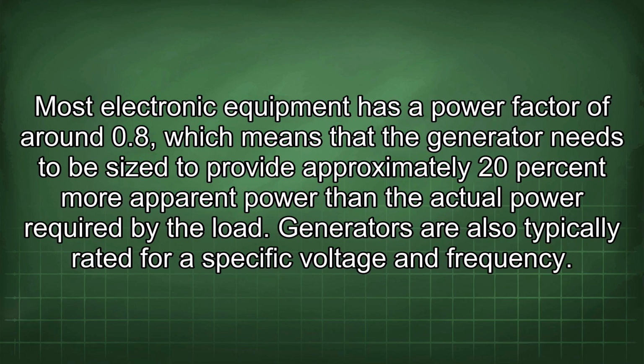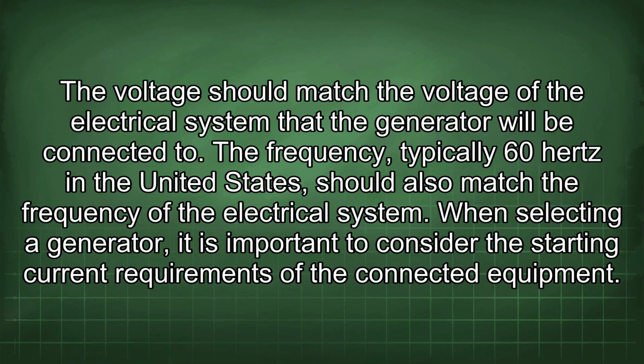Most electronic equipment has a power factor of around 0.8, which means that the generator needs to be sized to provide approximately 20% more apparent power than the actual power required by the load. Generators are also typically rated for a specific voltage and frequency. The voltage should match the voltage of the electrical system that the generator will be connected to. The frequency, typically 60 Hz in the United States, should also match the frequency of the electrical system.